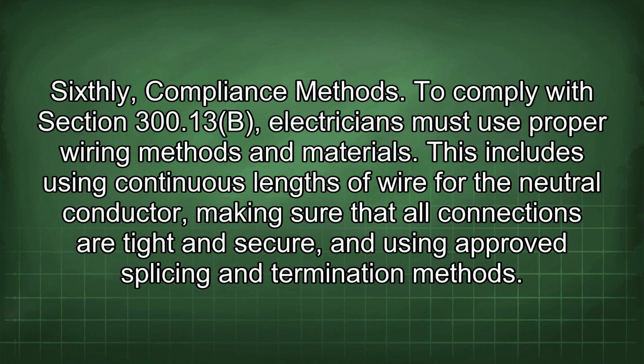Sixthly, compliance methods. To comply with Section 300.13b, electricians must use proper wiring methods and materials. This includes using continuous lengths of wire for the neutral conductor, making sure that all connections are tight and secure, and using approved splicing and termination methods.